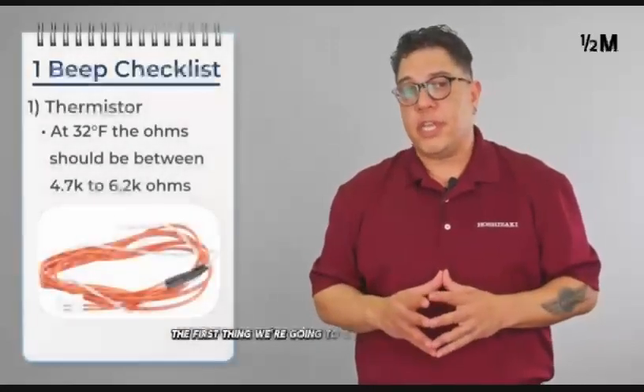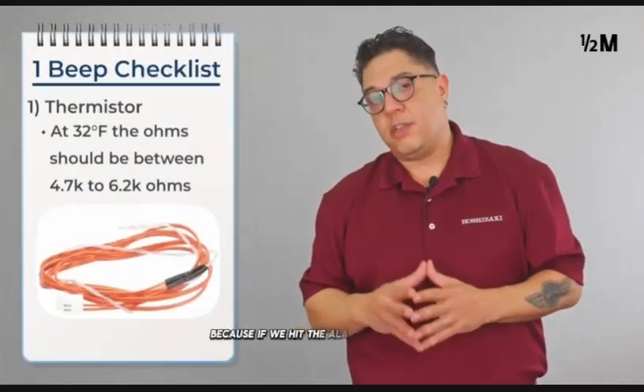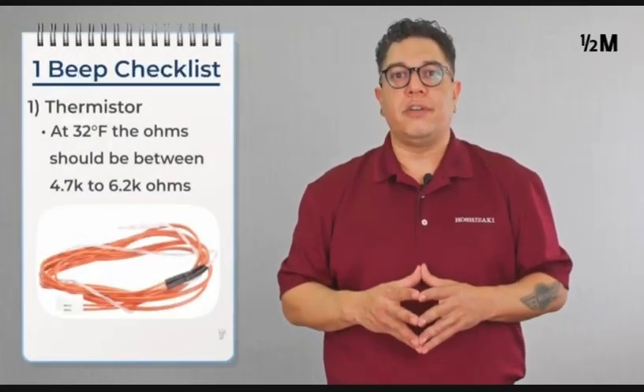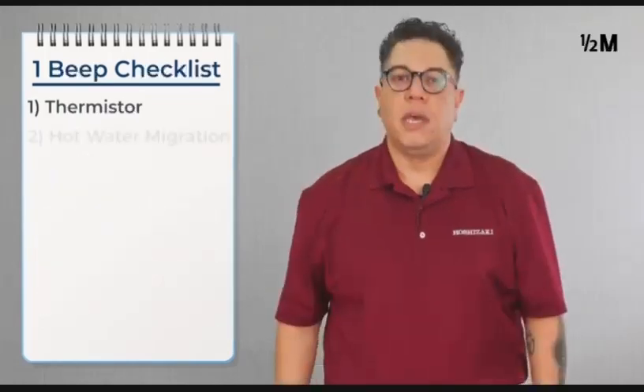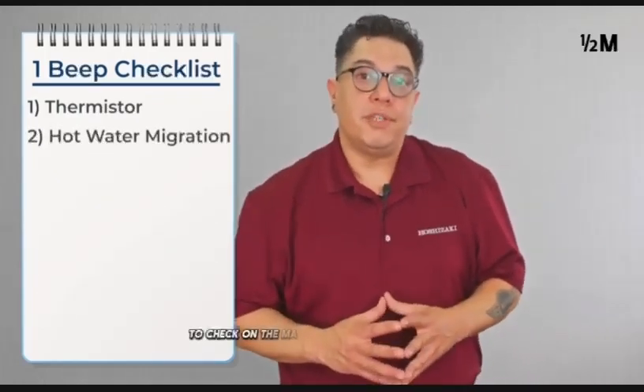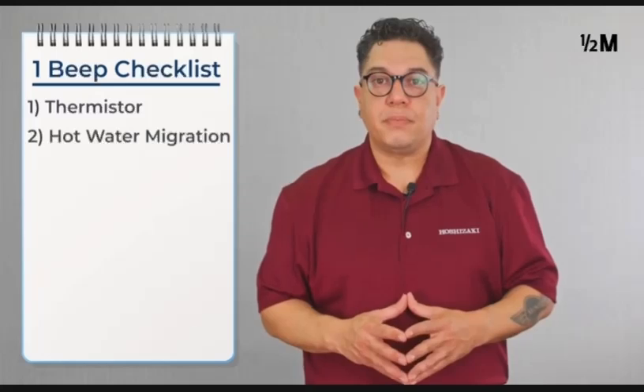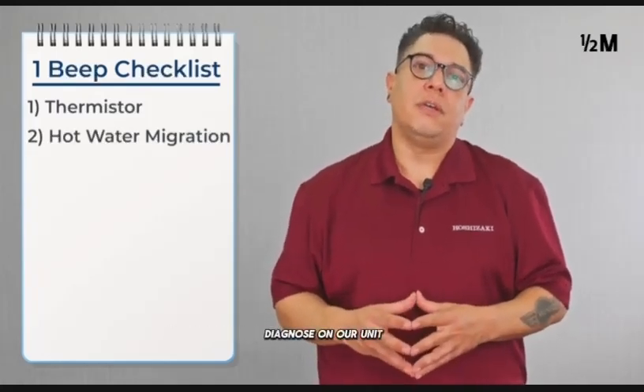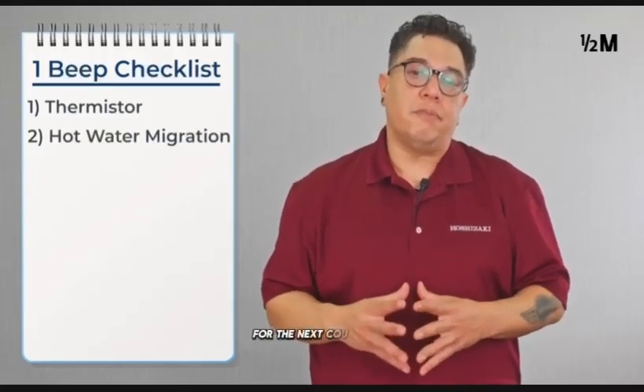The first thing we're going to check is the thermistor, because if we hit the alarm reset button and the alarm doesn't clear, that means the thermistor is shorted. The next step to check on the machine is hot water migration. Now, hot water migration is the most difficult thing to diagnose on our unit because you're not going to be monitoring the temperature of the water for the next couple days.